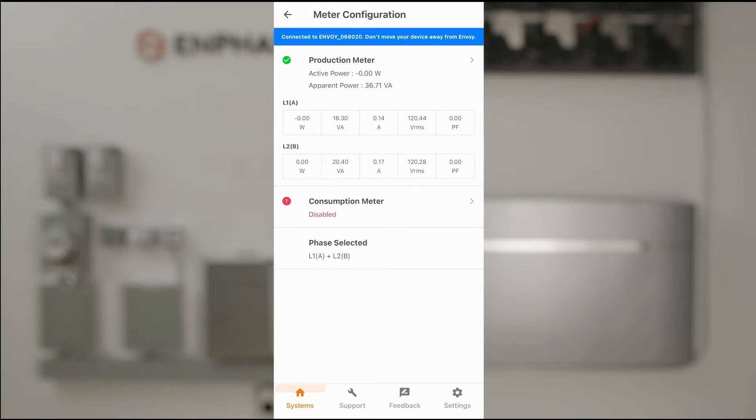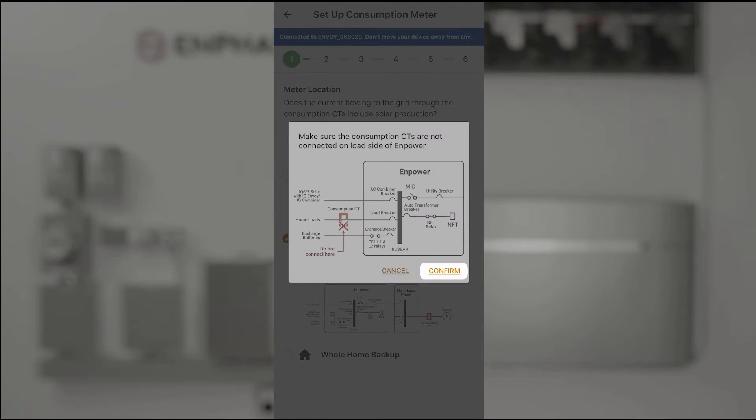Now we'll enable and configure the consumption meter. The first pop-up indicates that we absolutely must not install consumption CTs on the load side of Enpower. This is to verify that we understand this. We'll confirm by tapping Confirm.